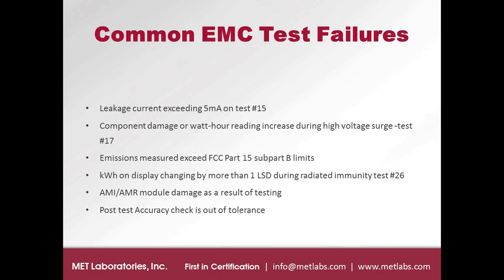We also see the kilowatt-hour or watt-hour readings on the display change by more than 1 least significant digit during the radiated immunity test. During this test we are not required to power the current circuits, so they are left open. Only the voltage is going through to the meter, and we monitor any other communications during the test. Sometimes, as a result of the test, which is a field of about 15 volts per meter, the display increases by more than what is called out in the spec. We also see AMI/AMR module damage as a result of the testing.